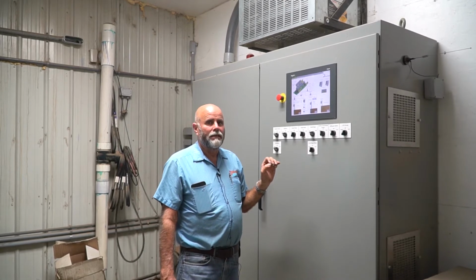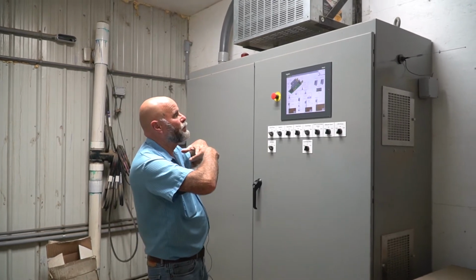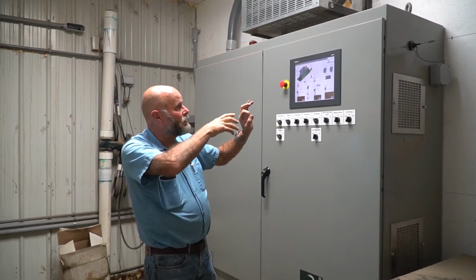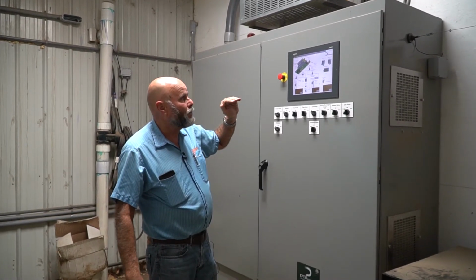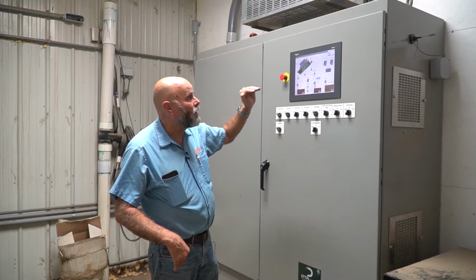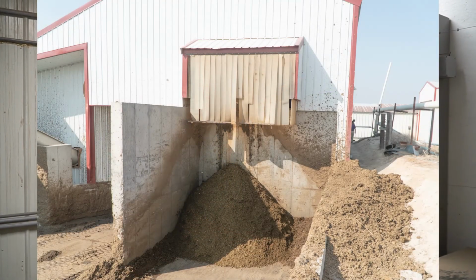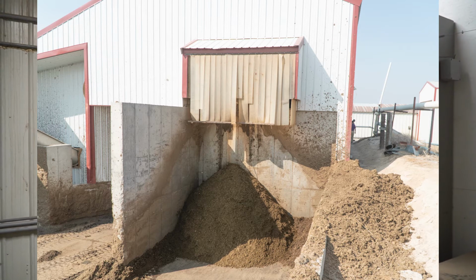Now the operation of the centrifuge: when solids are spun, they stick to the outside just like your wash machine does with your clothes. That auger, turning a little bit slower, pulls them solids at a constant rate and brings them up an incline inside the centrifuge, and it gets drier as it goes. So when it finally ends up dropping out of the centrifuge through nozzles on the end, it's dry enough to make a coned pile off the end of the centrifuge.